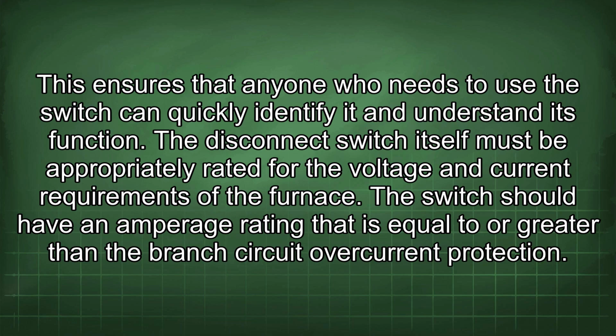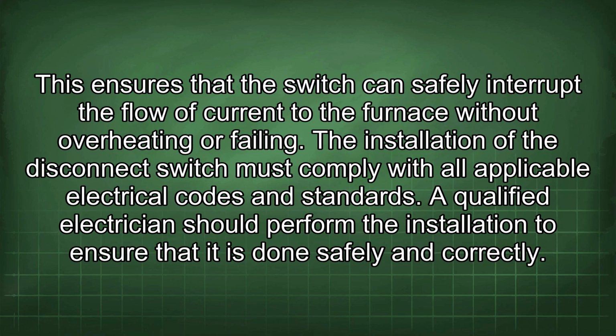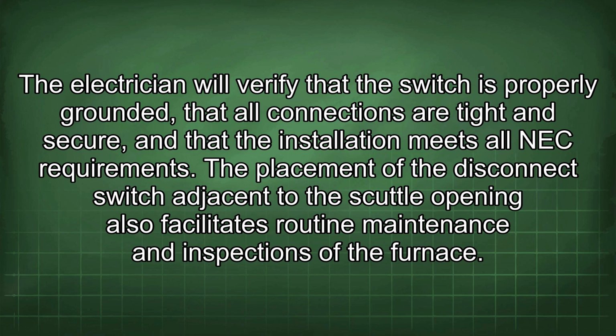The disconnect switch itself must be appropriately rated for the voltage and current requirements of the furnace. The switch should have an amperage rating that is equal to or greater than the branch circuit overcurrent protection. This ensures that the switch can safely interrupt the flow of current to the furnace without overheating or failing. The installation of the disconnect switch must comply with all applicable electrical codes and standards. A qualified electrician should perform the installation to ensure that it is done safely and correctly. The electrician will verify that the switch is properly grounded, that all connections are tight and secure, and that the installation meets all NEC requirements.